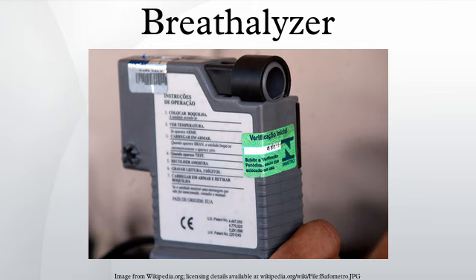Two breathalyzer technologies are most prevalent. Desktop analyzers generally use infrared spectrophotometer technology, electrochemical fuel cell technology, or a combination of the two. Handheld field testing devices are generally based on electrochemical platinum fuel cell analysis and, depending upon jurisdiction, may be used by officers in the field as a form of field sobriety test, commonly called PBT or PAS, or as evidential devices in POA testing.